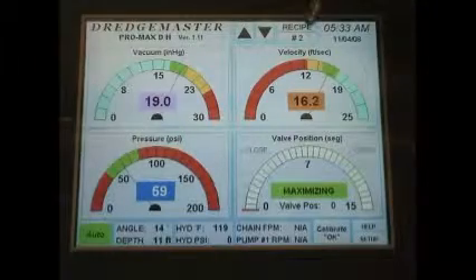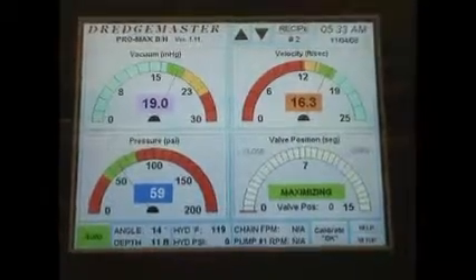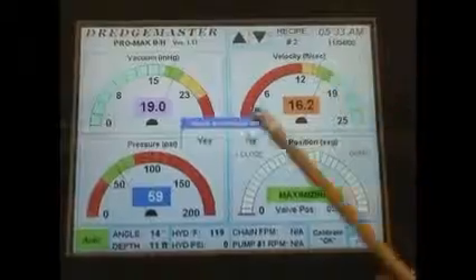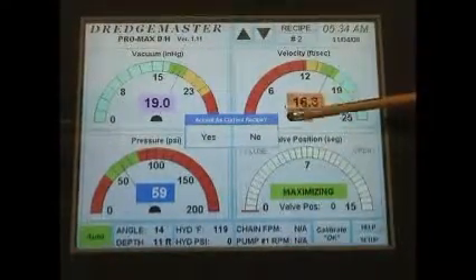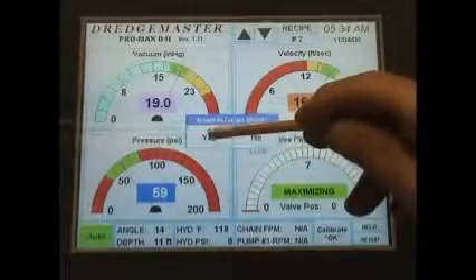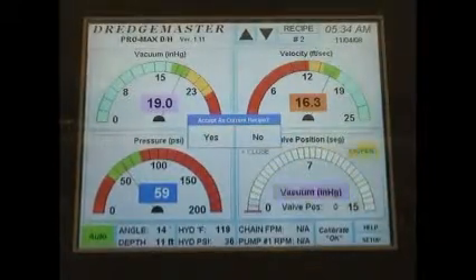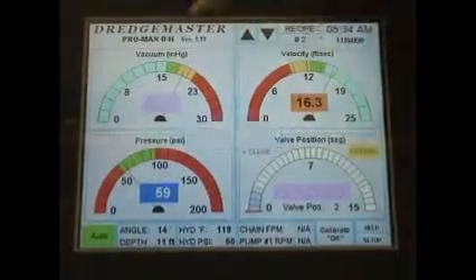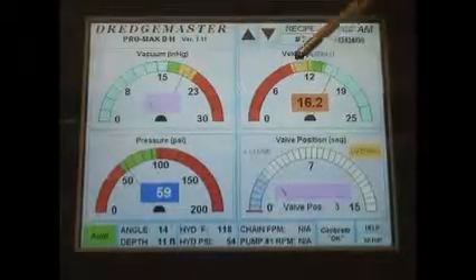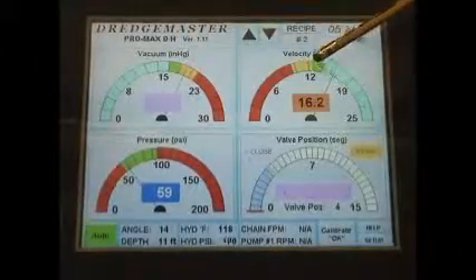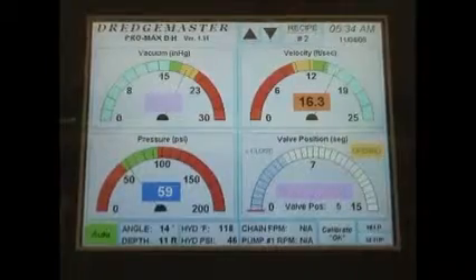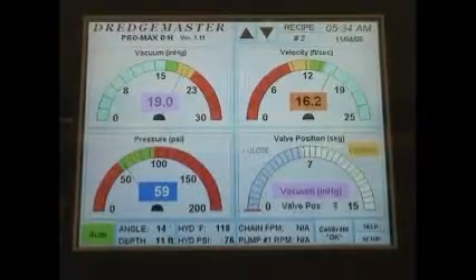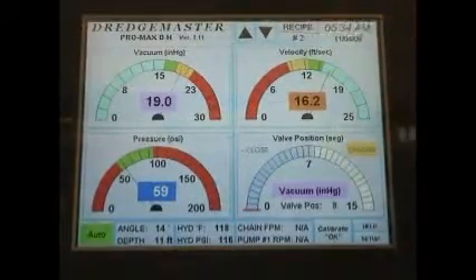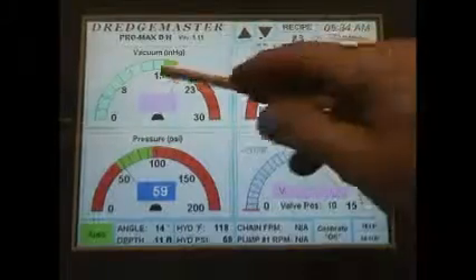He's going to select recipe number 2, and you're going to wait for about 5 seconds, and it's going to give you a prompt, accept as current recipe, and we're going to say yes because we want to go to recipe number 2. And as you can see, all the color zones have just changed. Recipe 2 had different parameters than what recipe number 1 had. Let's say we want to change the recipe number 2 parameters a little differently than what they currently are.